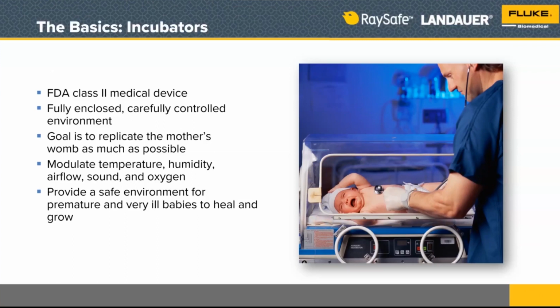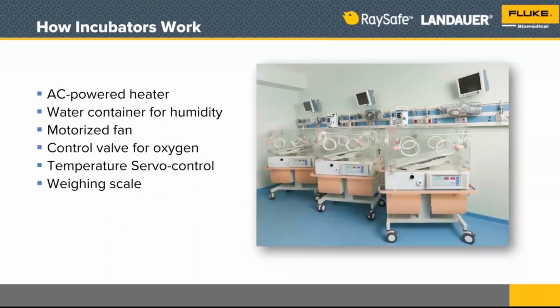So the incubator has an AC powered heater with a control circuit. It has a water container for humidity. Sometimes those are used and sometimes they're not. They were used a lot in the old days. Now we humidify the gases that the baby needs to breathe in different ways. It has a motorized fan to circulate not only the oxygen and humidification, but also to get the temperature to be equilibrated, or equal and uniform, within the infant incubator chamber. It has a control valve for oxygen, for how much oxygen we're going to deliver. And it has this temperature servo control that I talked about earlier, the AC powered heater.